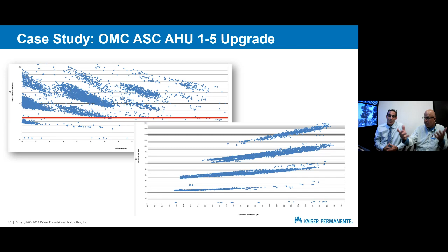This chart is also really interesting, just to look at the sheer difference. You and I see charts that look like this all the time, and by this I mean they look really weird, as opposed to what design engineers see. I was a design engineer for many years, and you see a number in a catalog that says this chiller works at this kW per ton, and then when you put it in service into a system, we see numbers that come out of that thing that are like this. They're all over the map. Right, it doesn't necessarily work. Yeah, and the chiller was running 24/7. It was not turning down. And it's a scatter plot.